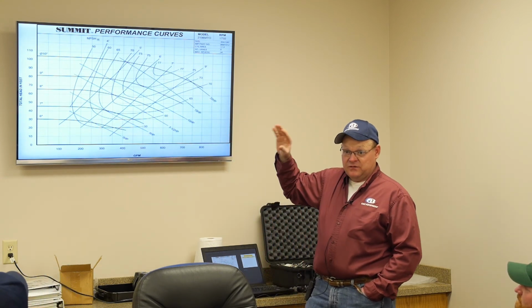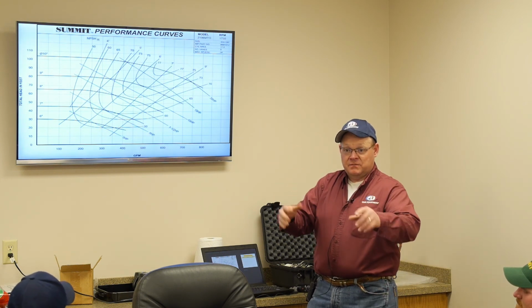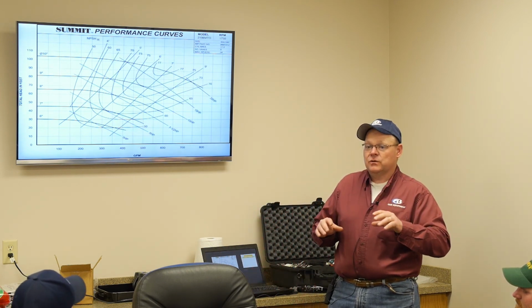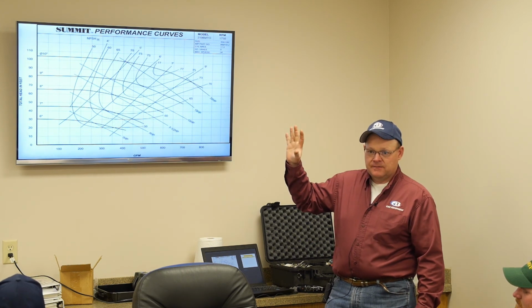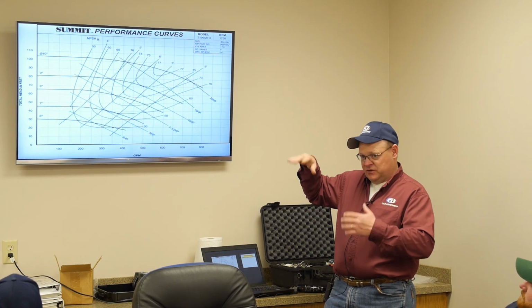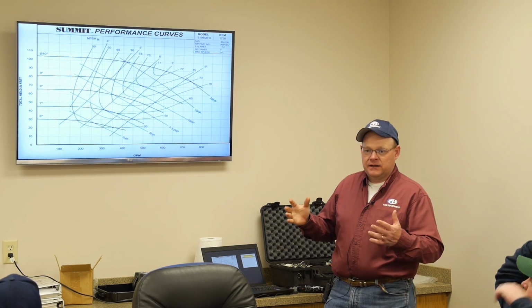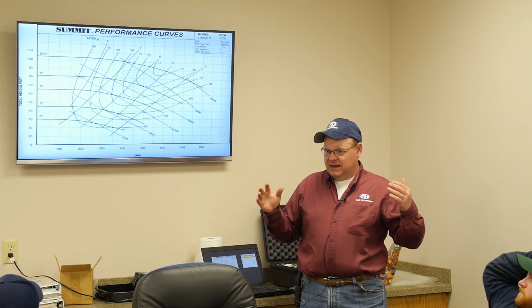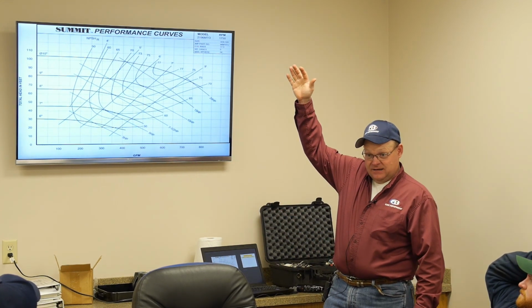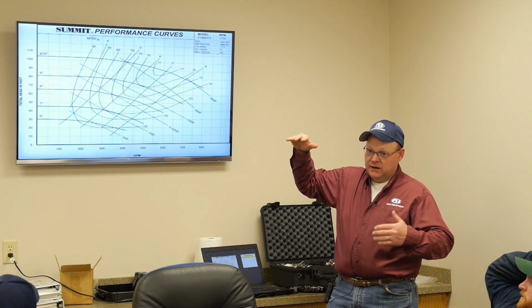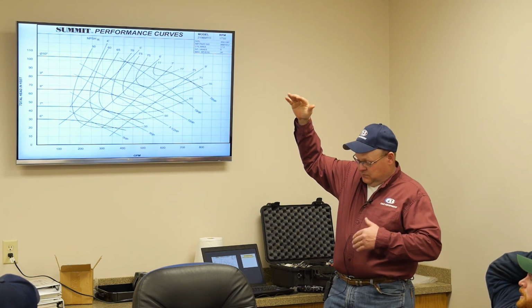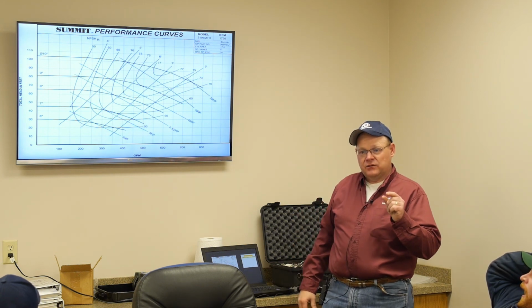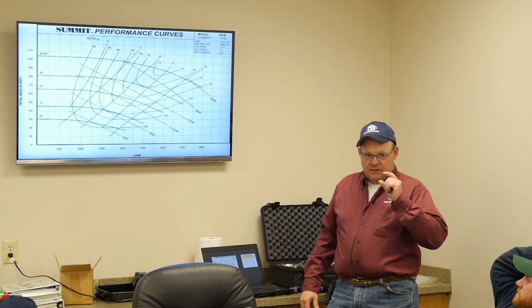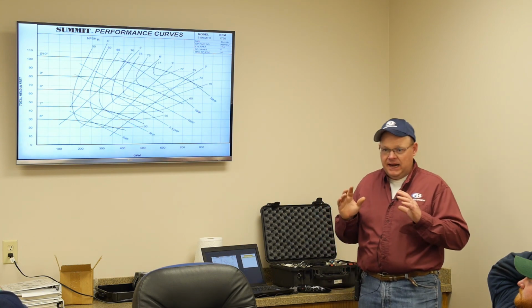Now, when it gets really confusing is when you throw in a variable speed, a potentiometer pot. Some of you have them in the plants, and they're a fantastic tool, because you may only want pressure. Because your pressure's changing in the plant, your system's going up and down, for instance, in an apartment building. Everybody gets up in the morning to take a shower, it's going to take a lot of water. So we're going to increase the pressure, right? Everybody goes out and walks off at 10 o'clock, but you still need 40 pounds of pressure on the 4th floor. Pump slows down. You're reading that 4 to 20 signal off that pressure transducer. So variable speeds, great things for centrifugal pumps. As far as that goes, variable speeds are great for any application most of the time.